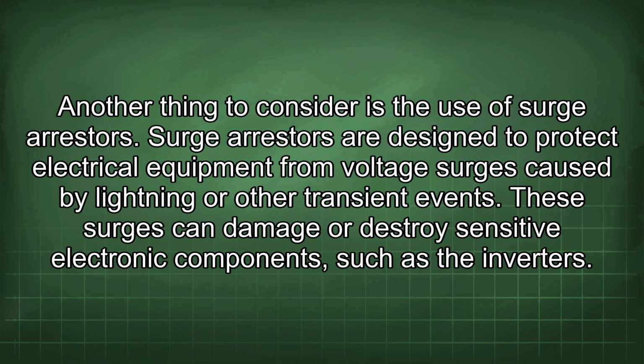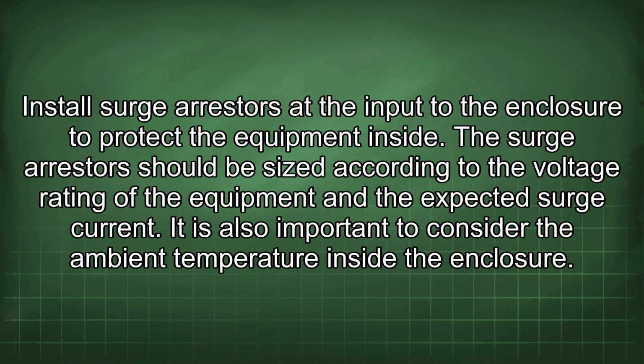Another thing to consider is the use of surge arresters. Surge arresters are designed to protect electrical equipment from voltage surges caused by lightning or other transient events. These surges can damage or destroy sensitive electronic components, such as the inverters. Install surge arresters at the input to the enclosure to protect the equipment inside. The surge arrester should be sized according to the voltage rating of the equipment and the expected surge current.